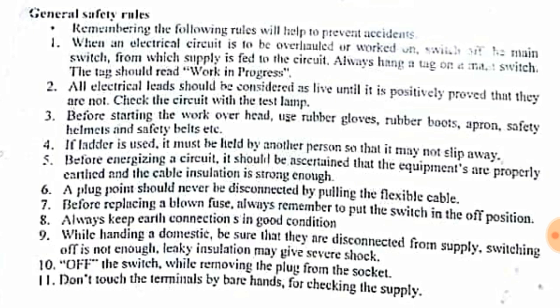Rule two: all electrical leads should be considered live until it is positively proved that they are not — check this with a test lamp. Rule three: before starting overhead work, use rubber gloves, rubber boots, apron, safety helmets, and safety belt wherever required. Rubber boots and gloves are used because they are insulating materials. Rule four: if a ladder is used, it must be held by another person so that it does not slip.